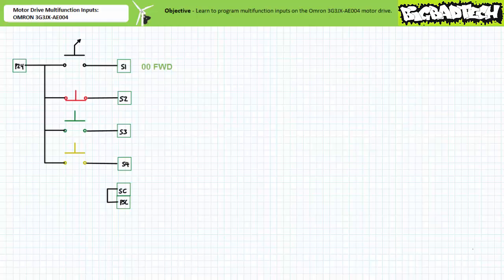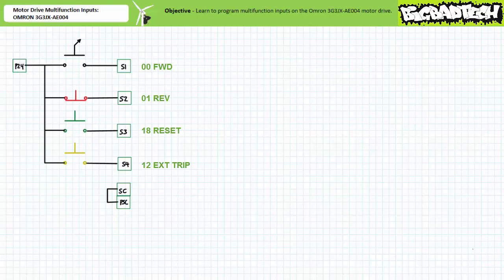The default function of input one is 00, forward. The default function of input two is 01, reverse. The default function of input three is 18, reset. The default function of input four is 12, external trip. Note the remote input device connected to input two is normally closed by nature, whereas all other devices are normally open. Upon handing off operation to the multifunction input terminals, the motor drive sees the presence of voltage on input two and rightly starts executing acceleration in the reverse direction as defined by the default function assigned to input two — reverse. The point again being that the motor drive is not a thinking machine, but something that does what it has been programmed to do.